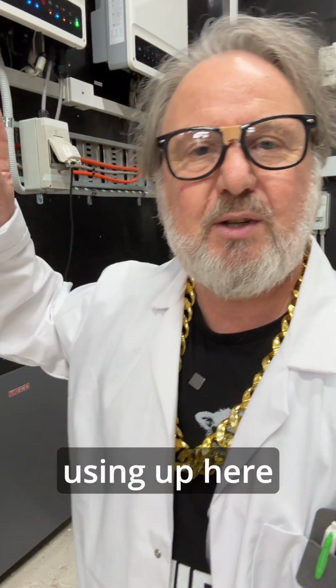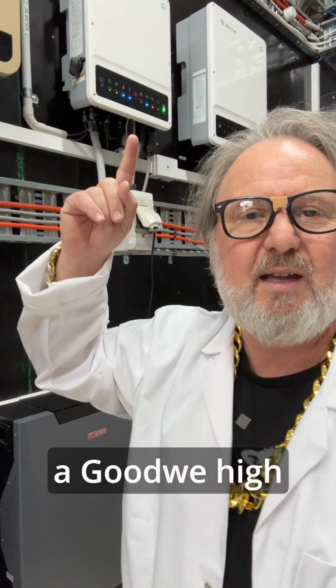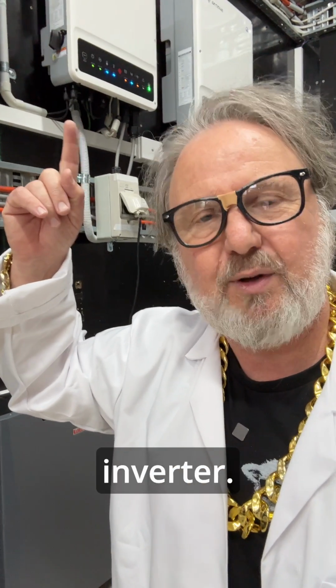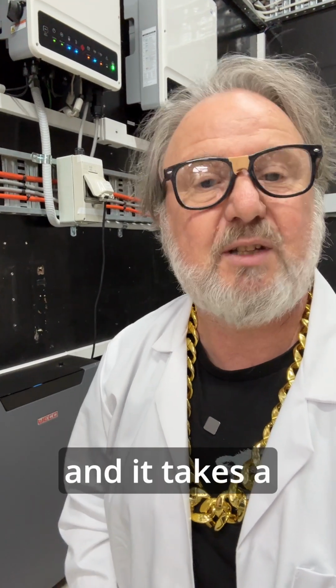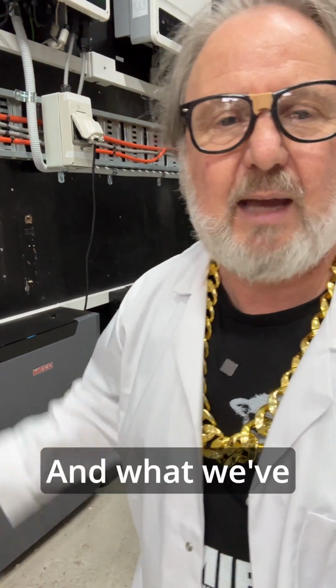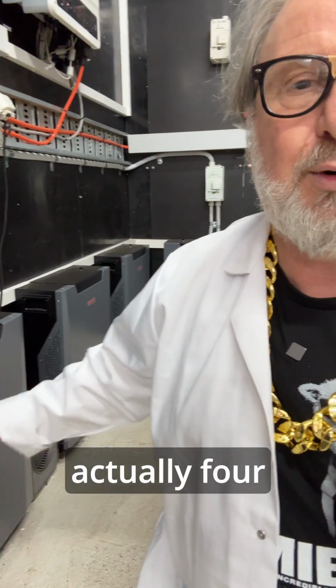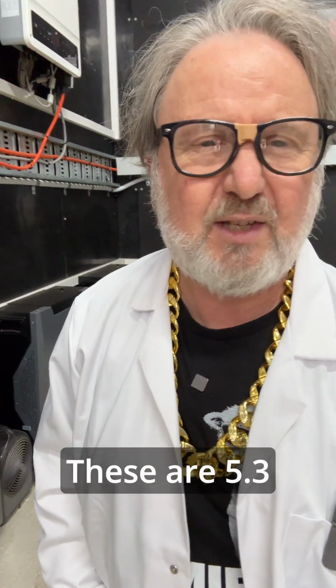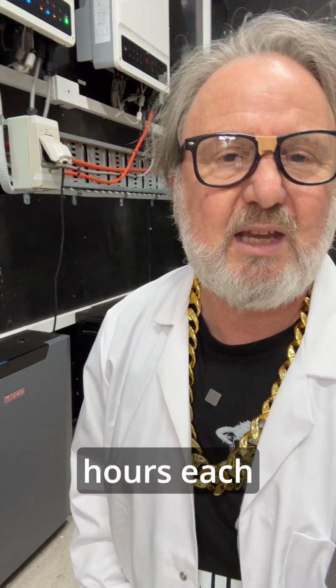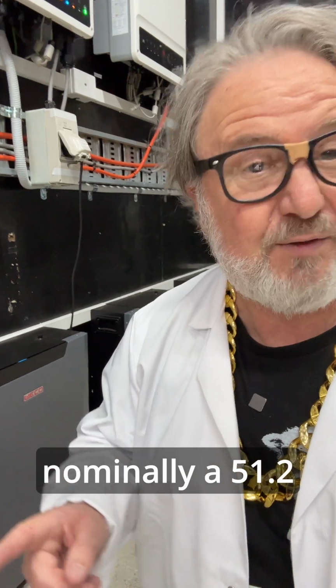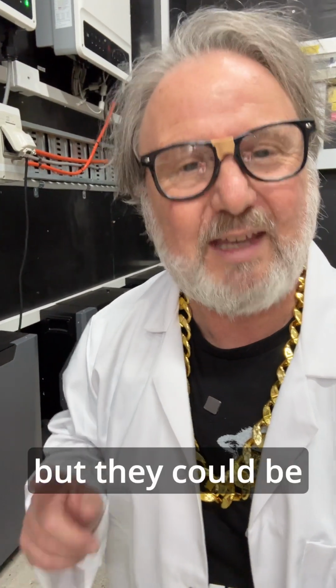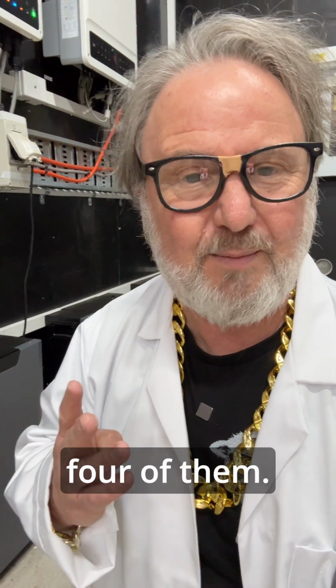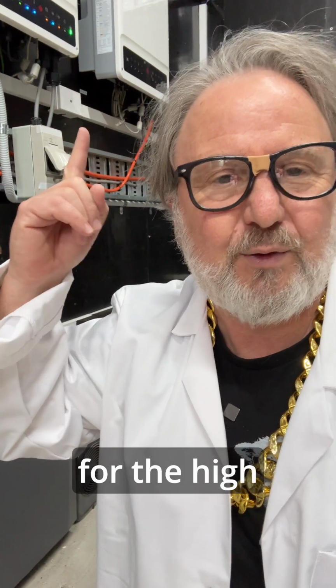So in this case, we're using up here a Goodwe high voltage hybrid inverter. This is the GW5000EH. It's a 5 kilowatt hybrid inverter, and it takes a high voltage battery stack. And what we've got here is actually 4 of the Weco batteries. These are 5.3 kilowatt hours each, and they're nominally a 51.2 volt battery, but they can be connected in series. Because we've got 4 of them, that'll give us a 200 and something volt string, which is ideal for the high voltage Goodwe inverter above me.